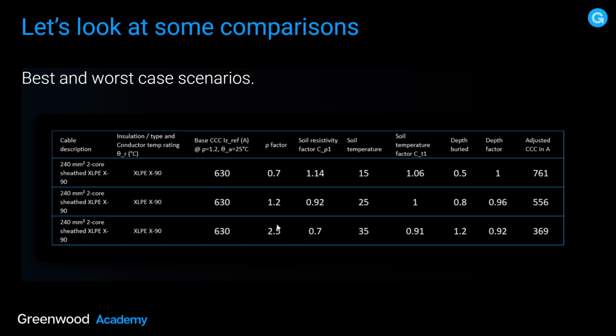Absolutely ridiculous soil, 2.5 thermal resistivity. You're talking a 35 degree soil temperature. You're talking about a 1.2 meter bury, and look at what it does to the current carrying capacity after all that derating, 369 amps. So hopefully you're starting to get an understanding of that intrinsic relationship between all these factors. Now we're going to look at a step-by-step process that you should go through ideally to assess what's needed for these solar farms from a cabling and burying direct or in conduit configuration. Let's get stuck into it.